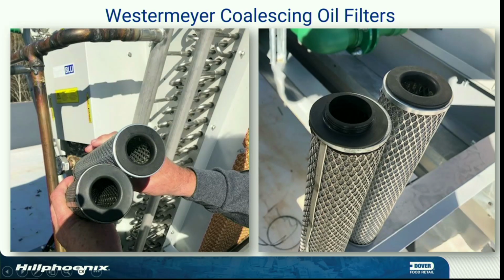Westermeyer redesigned their filters about two years ago. They used to have hard gaskets that were glued on. You remember those? Yep. That gasket was stiff. It was that hard. Well, they redesigned it. They didn't say anything to anybody. We all of a sudden started getting these rubber donut gaskets. Well, these rubber donut gaskets, you can take them with your fingers and pinch them shut. What's going to happen to them under compression? They're going to compress, right? They never changed the mounting point either. So there's actually a little bit of room in there for movement.